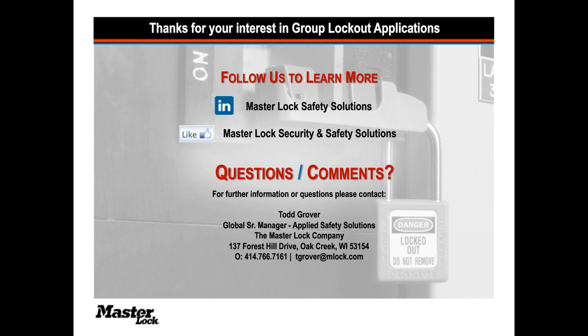Okay. Now, the best form that takes, and what OSHA holds to be the right of the authorized worker, is to visually inspect for themselves and test for a zero energy state. In scenarios where there's just a few people participating, the idea that either you physically test or you observe someone else testing so that you achieve a comfort level with the testing, that is the right of each authorized worker.